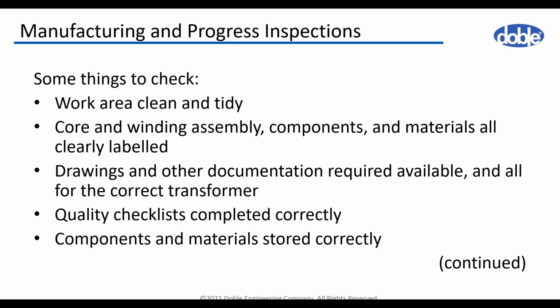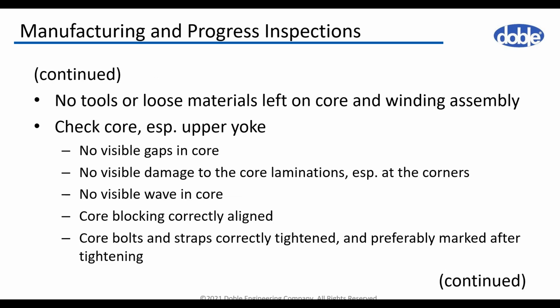We also check the quality checklists, if they are completed and filled correctly, including NCRs issued during assembly. We would like to see if the materials and components are stored correctly also. During inspections, we don't expect to have tools or materials left on the core and winding assembly. They could be easily forgotten there and cause significant damage during testing, or even worse if these damages happened in service. Some manufacturers block the openings of the core and winding assembly using simple methods like crushed paper in order to avoid contaminations being trapped.